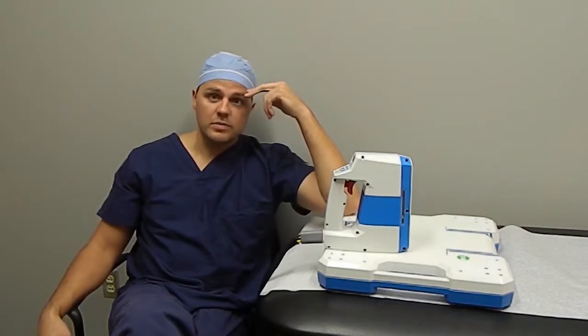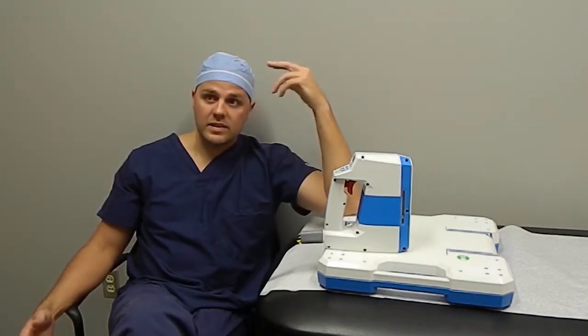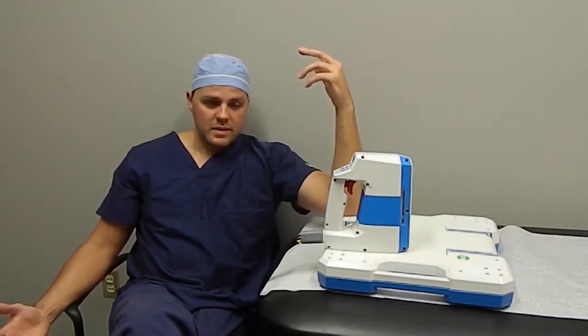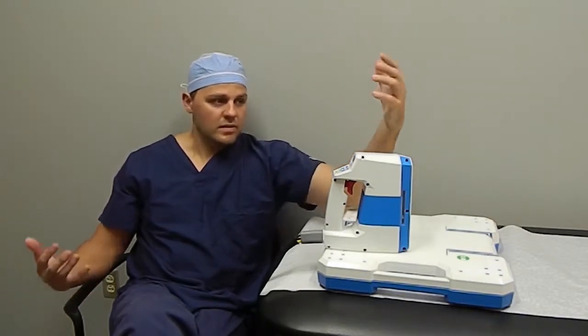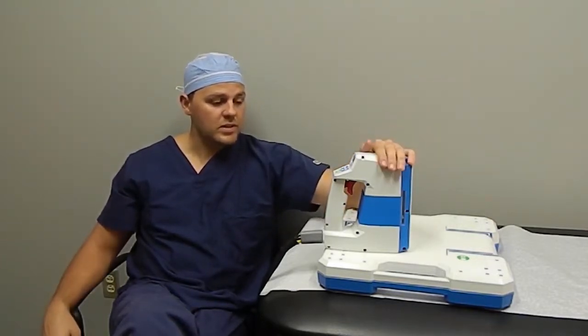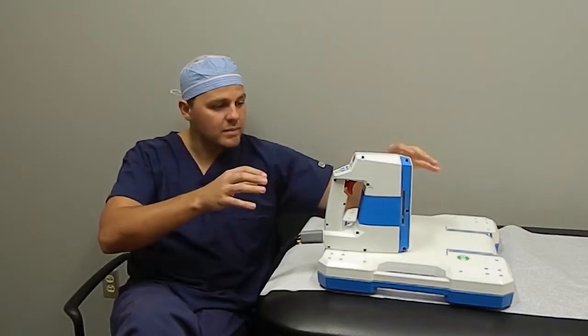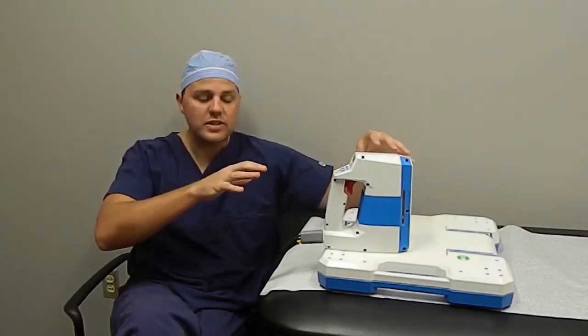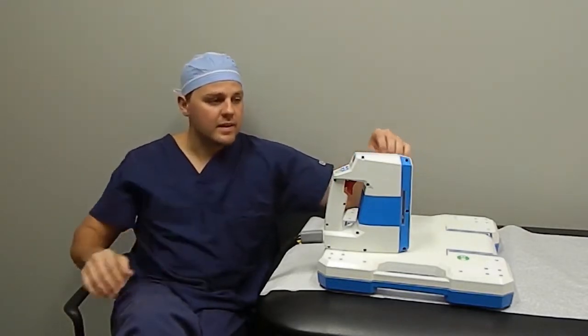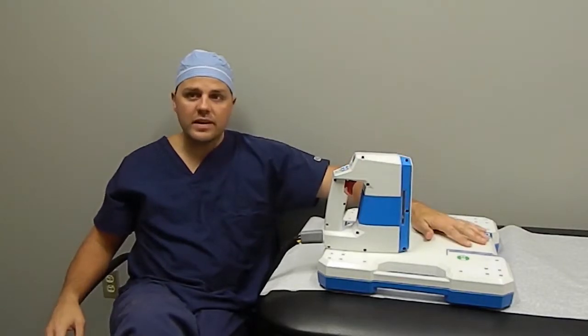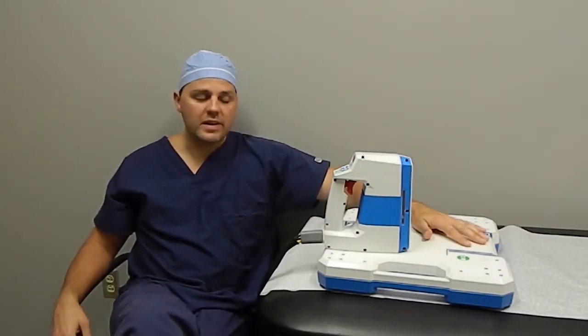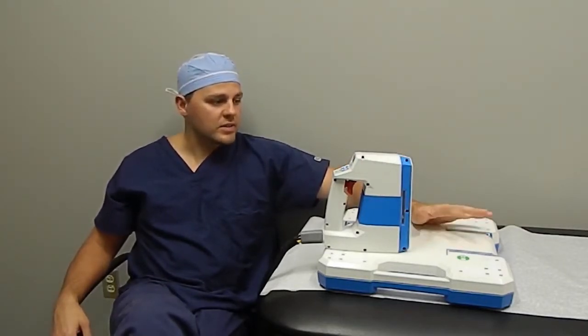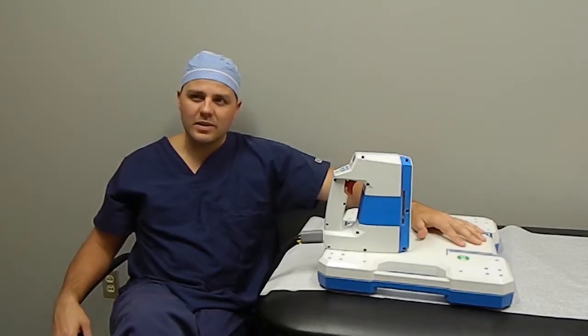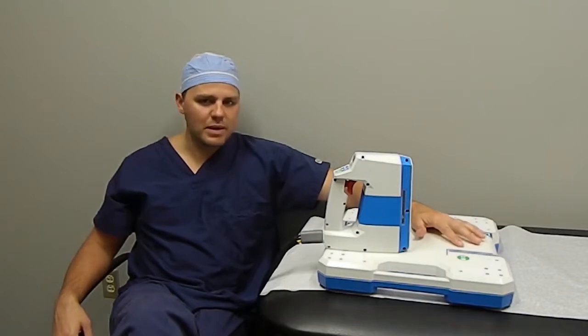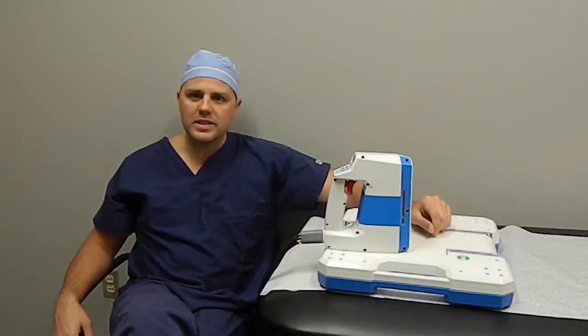And that's really the ingenious part, being able to satisfy the specifications of the FDA through our intellectual property, which is basically changing the shape of the conical beam, knowing where we're at in position and time so they're always centered, tracking this at all times. Those are really the genius part of the IP. But then also miniaturizing the X-ray tube to get us a lower radiation but a clearer image, and being able to get us a more accurate image every time, because a lot of times if you bump the table or you bump the C-arm, you get a blurred image.